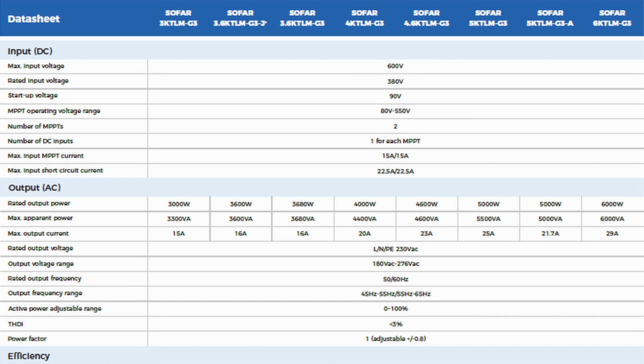It's not battery ready. Whatever it's going to produce is going to support the load, and the rest will be fed into the grid or exported to the grid. Okay. Max input voltage is up to 600 volts. Make sure it's never ever hit that because you're going to damage the inverter. You're basically going to burn the MPPTs in it. Rated input voltage, which is the sweet spot of the inverter, is 380 volts. Okay. Startup voltage of 90 volts. Startup means that the inverter HMI will wake up. It doesn't mean production will start at that.